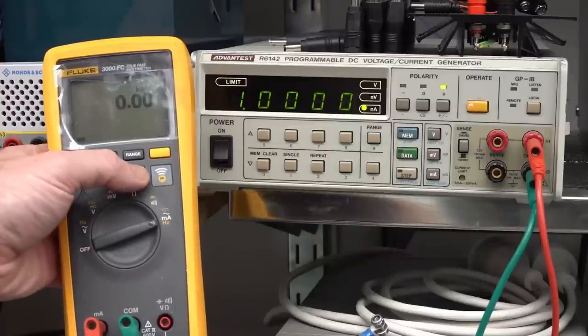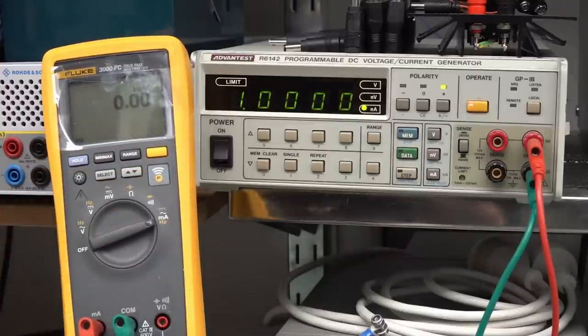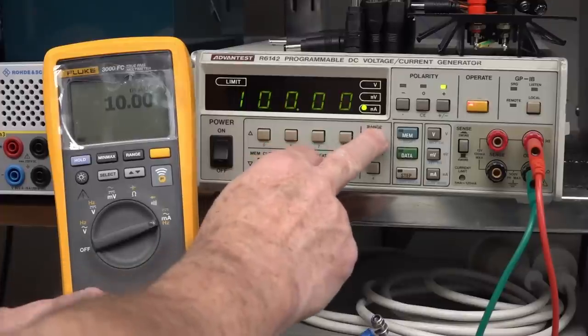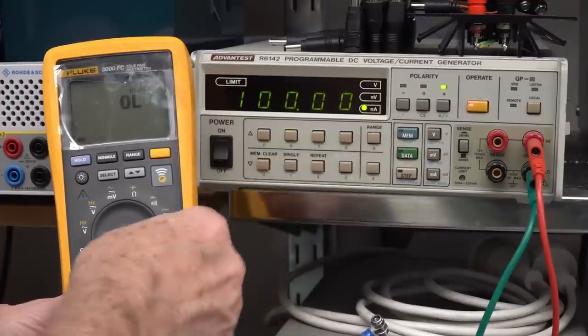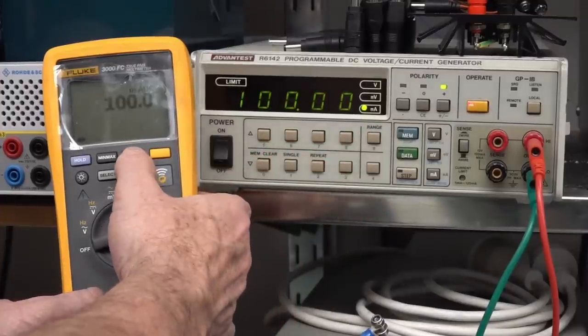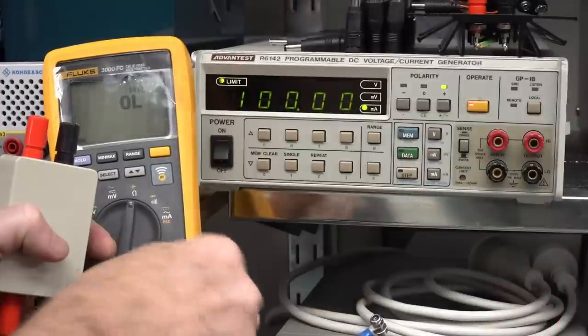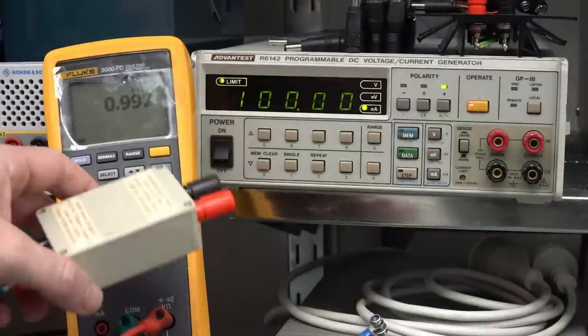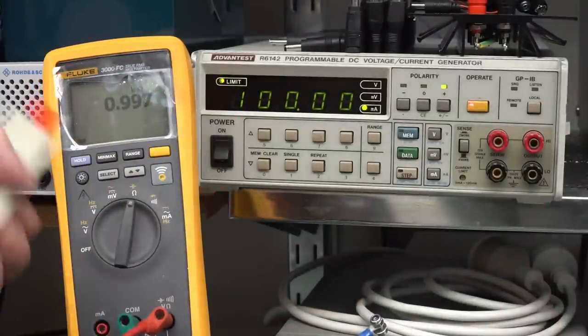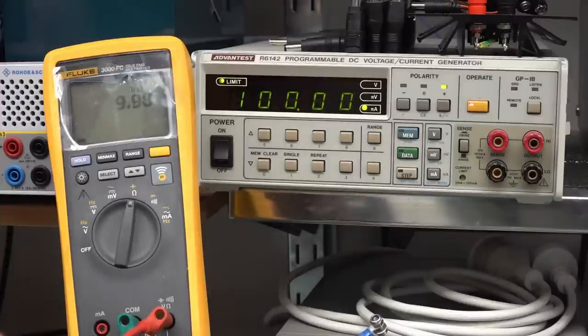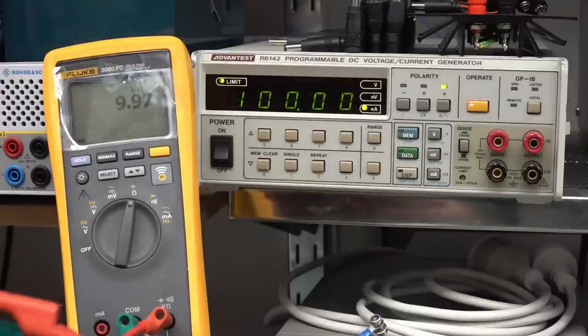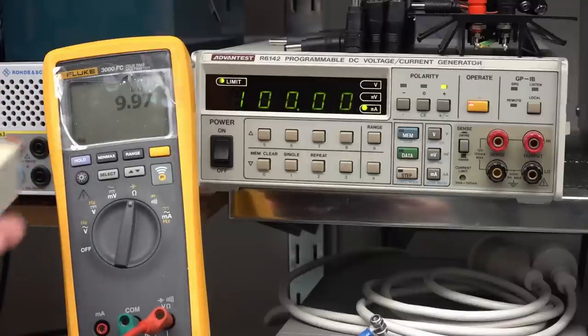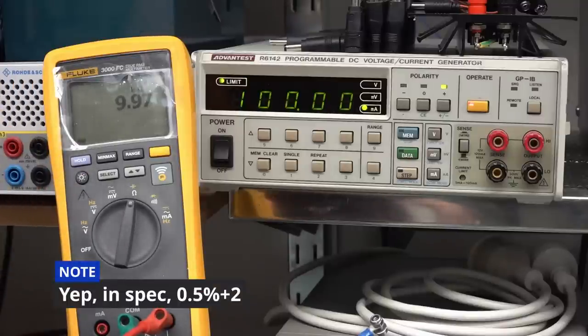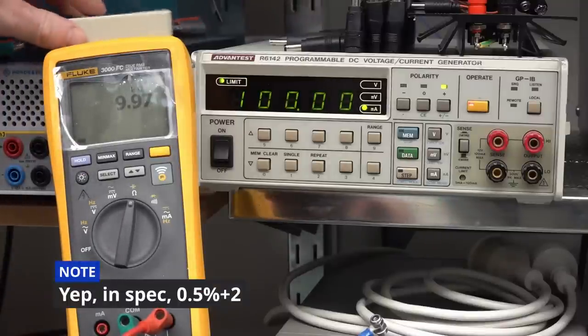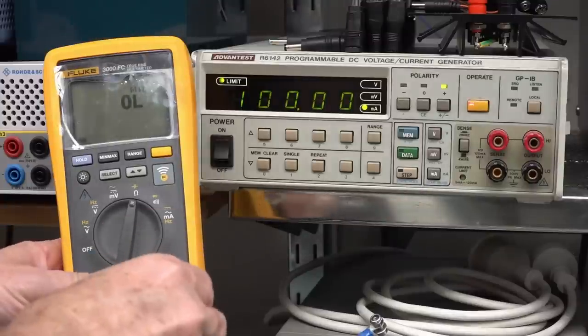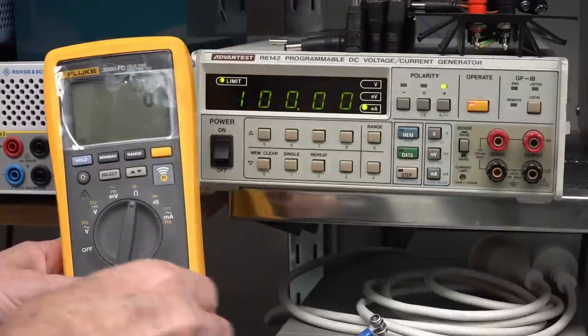Select. And up and down arrows. It's all beeping. It all works. 10 milliamps. 100 milliamps is over range. There we go, 100 milliamps. Measure resistance, hook up my calibrator box, my 1K, yep, near enough. My 10K, yeah, near enough, there's nothing in it, really. This is not a super accurate meter on resistance, I don't think, but that's good enough. That's within spec.